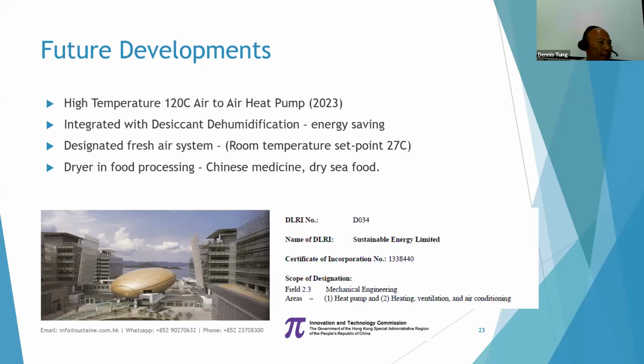So for the heat pump development and the desiccant development, as I mentioned before, heat pump can achieve 120 degrees Celsius leaving air temperature. I think this could be found in the market next year. And this very high temperature gives us a very good potential to think about innovative design in this building to achieve much more energy saving. Also, integrating this heat pump into a desiccant dehumidification process can provide better saving, even at large.